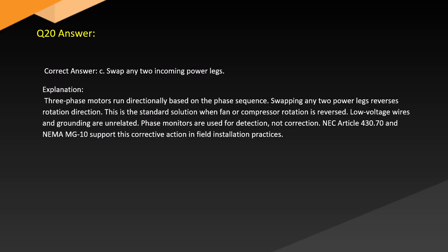Answer. Correct answer: C. Swap any two incoming power legs. Explanation. Three-phase motors run directionally based on the phase sequence. Swapping any two power legs reverses rotation direction. This is the standard solution when fan or compressor rotation is reversed. Low-voltage wires and grounding are unrelated. Phase monitors are used for detection, not correction. NEC Article 430.70 and NEMA MG10 support this action in field installation practices.